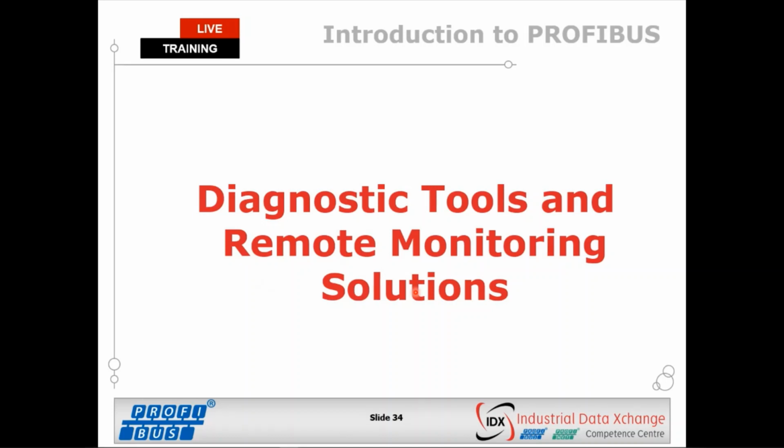So, diagnostic tools and remote monitoring solutions. Unfortunately, a multimeter is not a very good diagnostic tool for a PROFIBUS network. Great to check the power supplies, but because it's a high-speed digital communication system, you actually need an oscilloscope to capture that image, or possibly a bus tester to allow you to have a look into that network. You're pretty much blind without that.